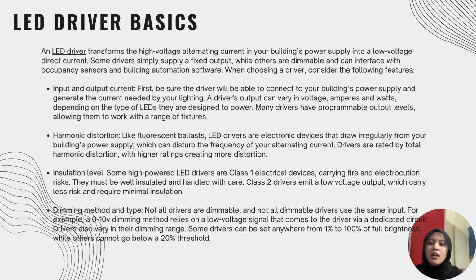Harmonic distortion. Like fluorescence ballast, LED drivers are electronic devices that draw irregularly from your building's power supply, which can disturb the frequency of your alternating current. Drivers are rated by total harmonic distortion, with higher ratings creating more distortion.